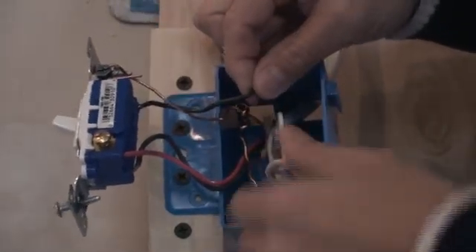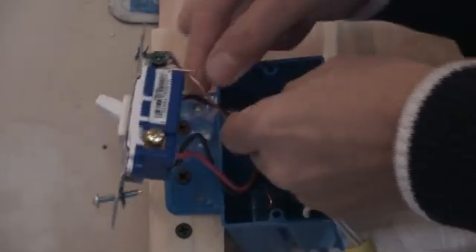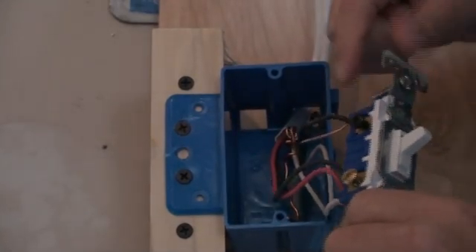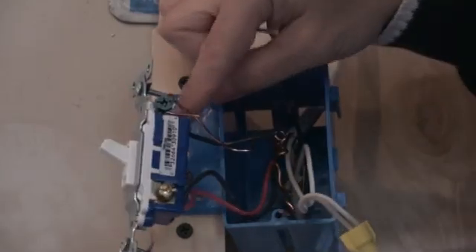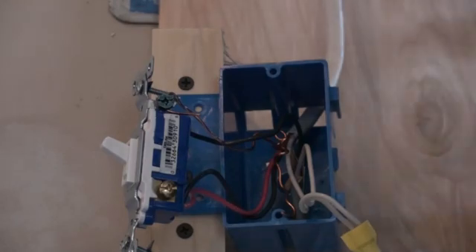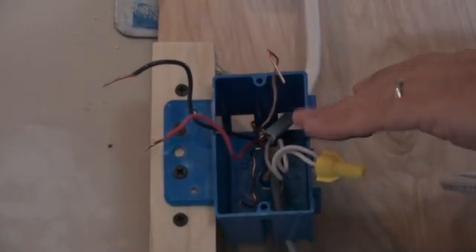The important thing you want to remember before removing the switch: take the hot wire coming directly from your electricity here. Remember you have the white, the black which is the hot, connected to the black screw here. So you want to put a tape on this black. This is important when you replace the switch. Before we start working and opening the box, make sure that the power is off.